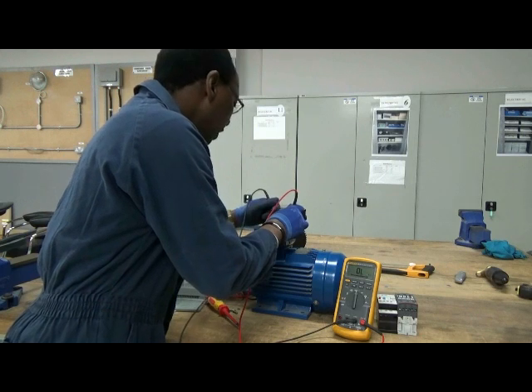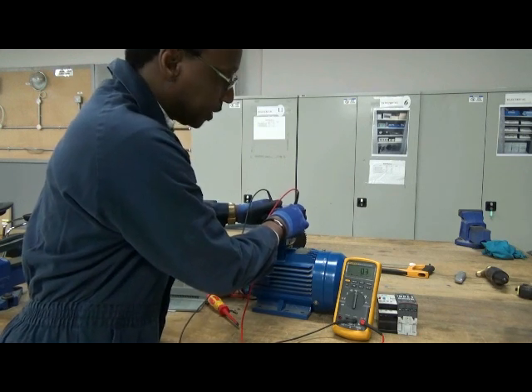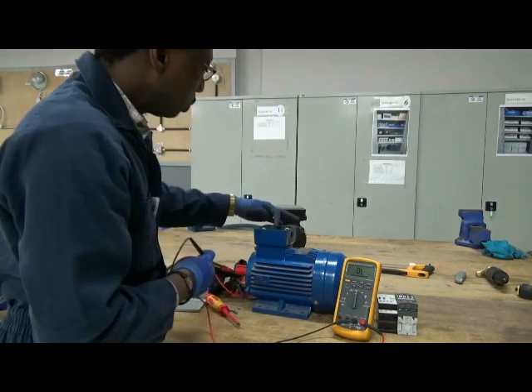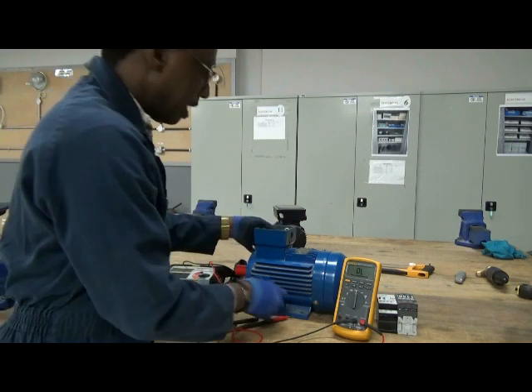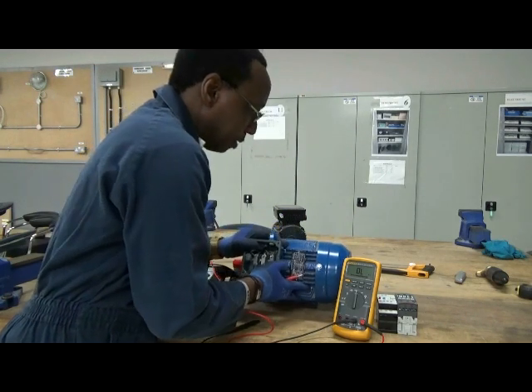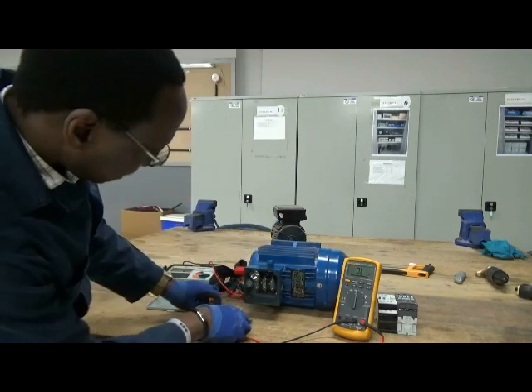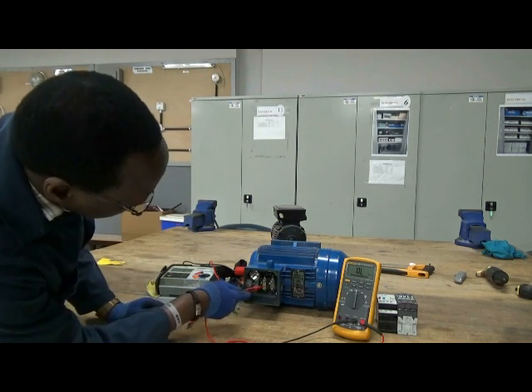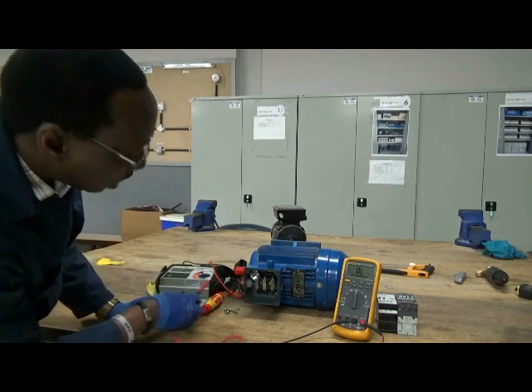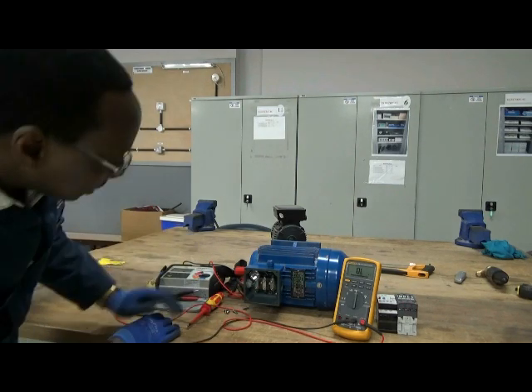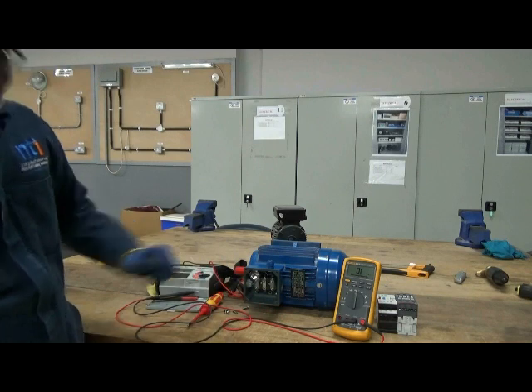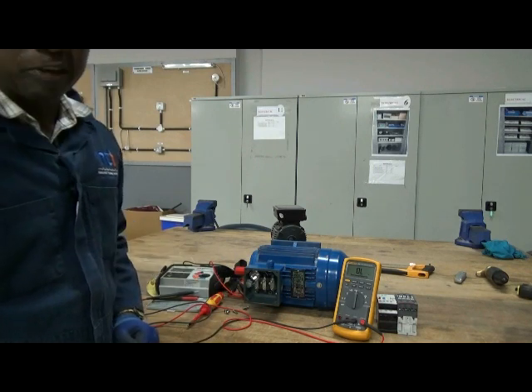So I'll put one probe on one position and another one on the next. As you can see there, I'm getting a very low resistance. There are actually some short-circuiting bars that are inside. I have to remove them. If I tilt this machine this way, probably everybody will be able to see well. Okay, so these are the short-circuiting bars. I have to remove them, I have to take them out so that we can start the measurement. Sorry for that. I have to remove the short-circuiting bars first.